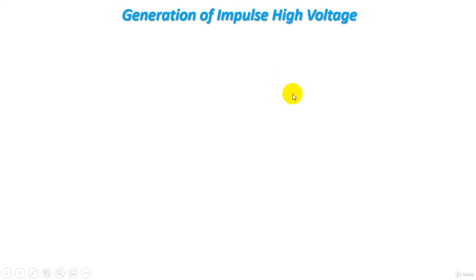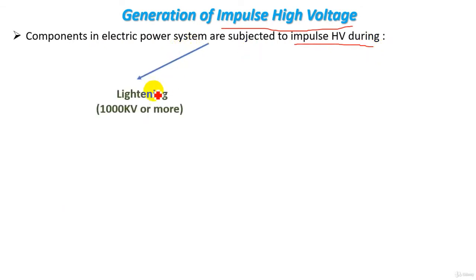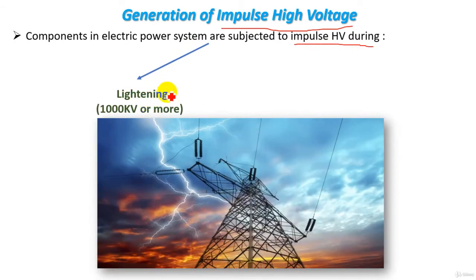This tutorial is about impulse high voltage, which is very important to study and understand because components in electric power systems are subjected to it during lightning. When lightning strikes, power system components can be subjected to 1000 kilovolts or more. This voltage is very high and may cause damage, so high voltage components should be tested under this voltage — meaning we must produce impulse high voltage in the lab to test insulators and high voltage components.